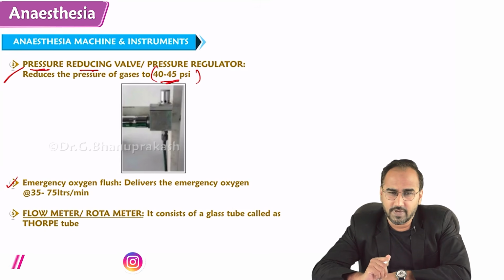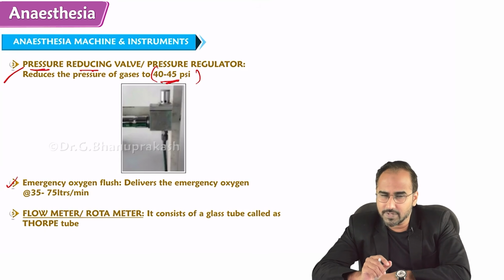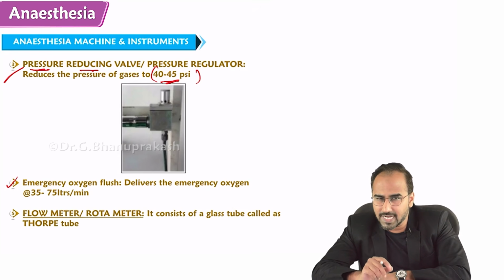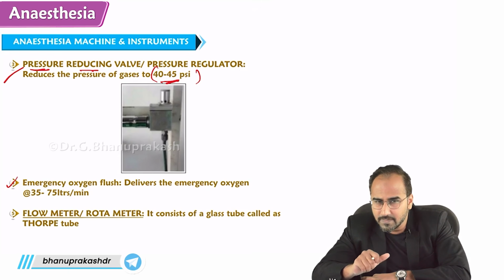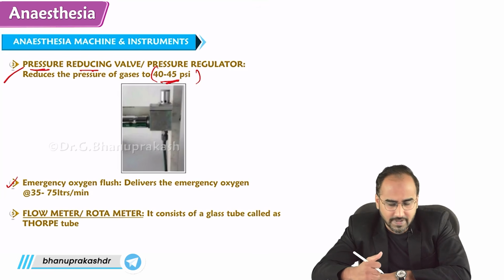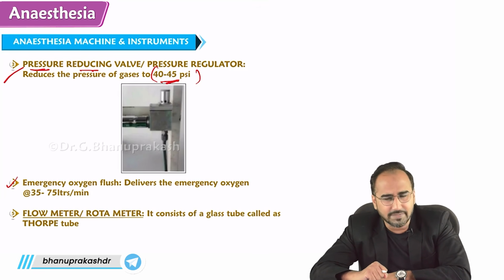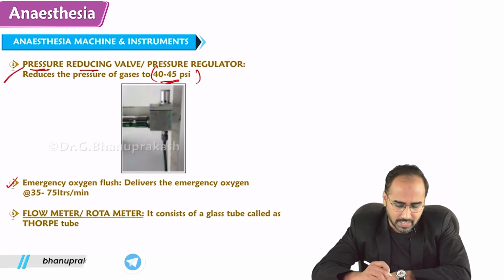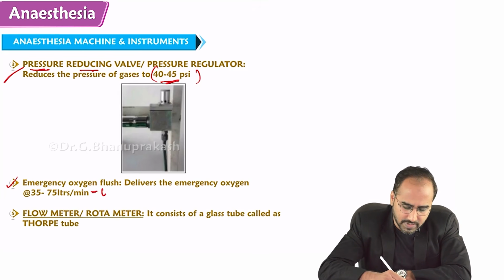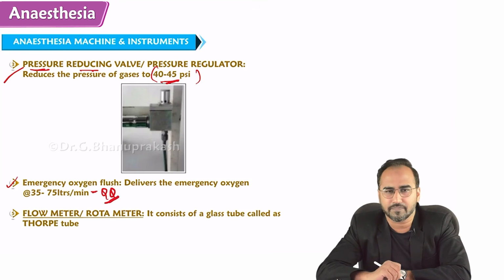Emergency oxygen flush: where the green color pipe was coming out, no, the breathing circuit. Beside the breathing circuit there was a button. When you push this button, it will deliver oxygen at a tremendous rate, I told you. In cases of hypoxia, that is emergency oxygen flush. It delivers oxygen at a rate of 35 to 75 liters per minute.